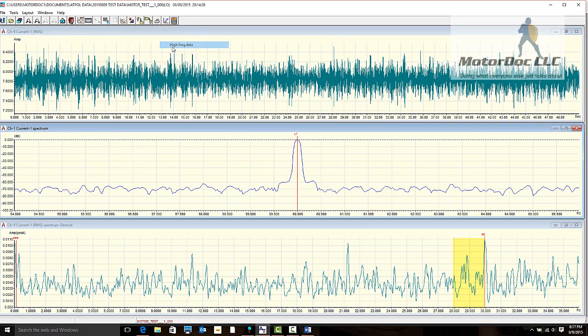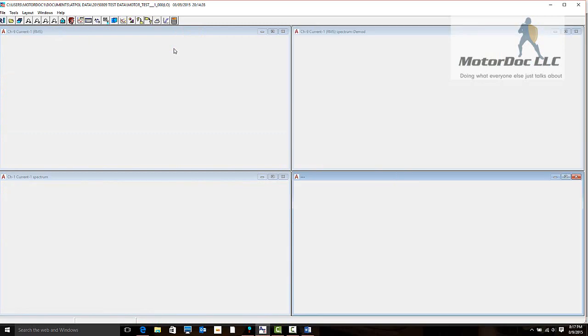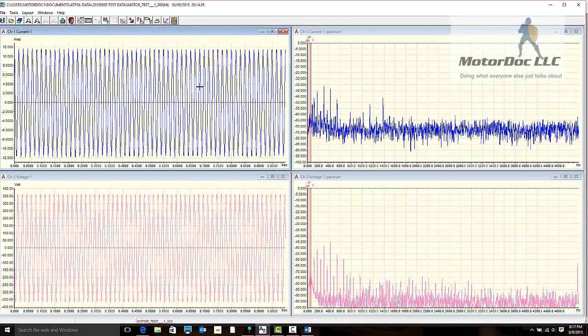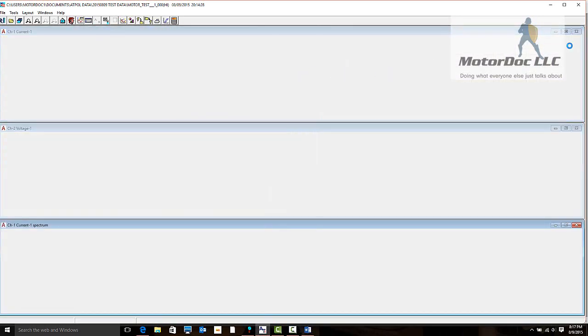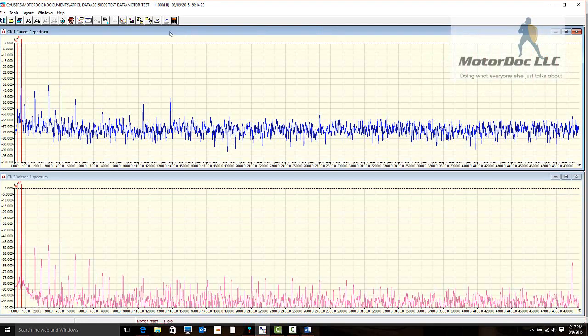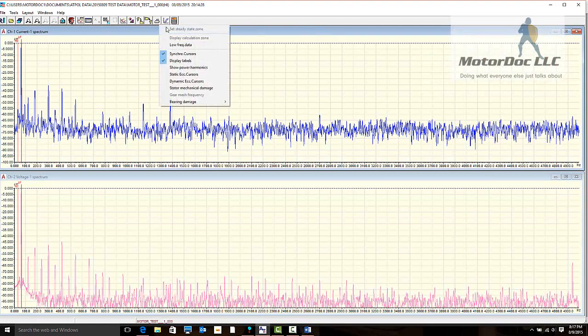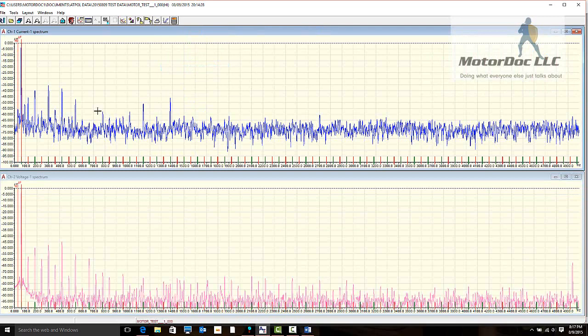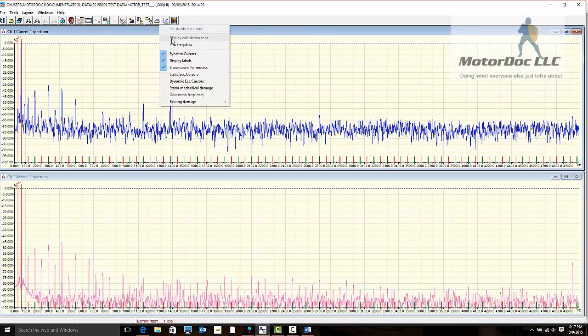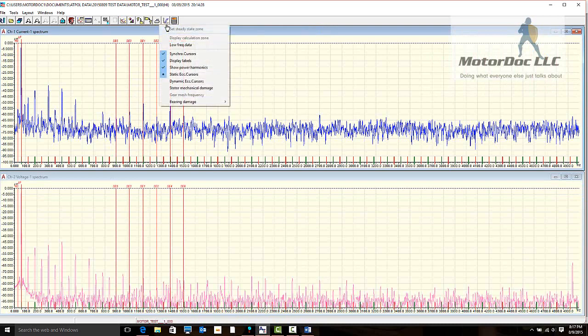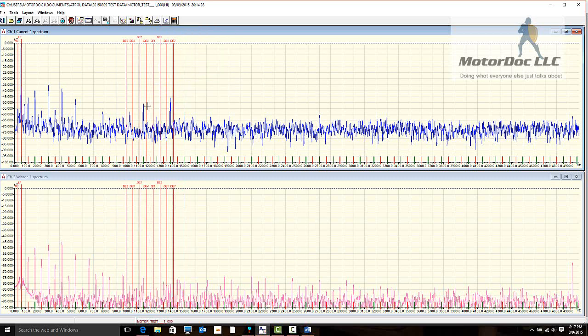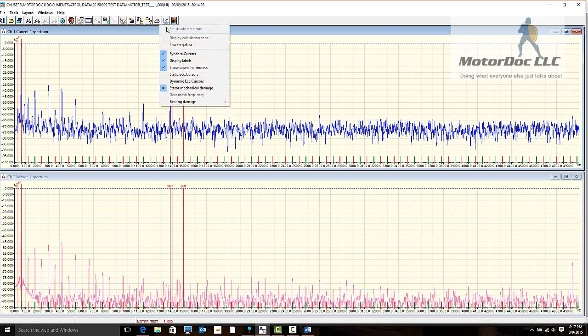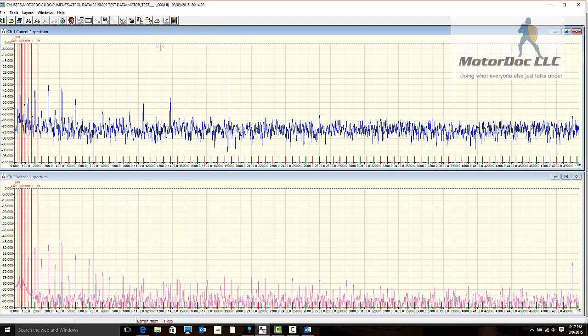This is going to show me what my waveforms look like in voltage and current. And if I zoom in, it will also show me my higher frequency data that I can now analyze. Because I have all that information, I can have it show me power harmonics first. So anything above this in an induction motor, I'm not going to pay a lot of attention to. Static eccentricity, which it definitely has some. Dynamic eccentricity, which it does not. Any type of stator mechanical, which it appears it does have some.